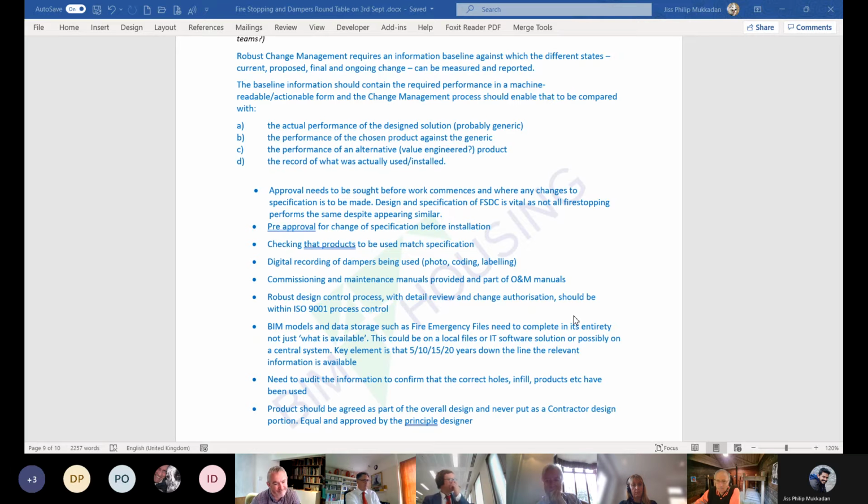This comes down to my point of space, and if somebody sees a beam with some nice holes in it, they stick stuff through it. But there is no test evidence for dampers and ducts going through those holes in beams. No. There could be, but there isn't.